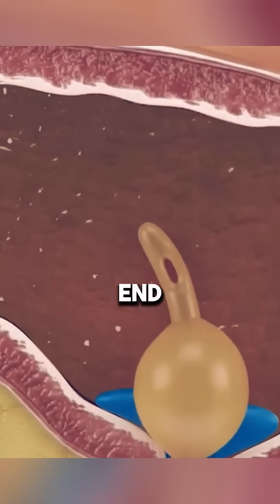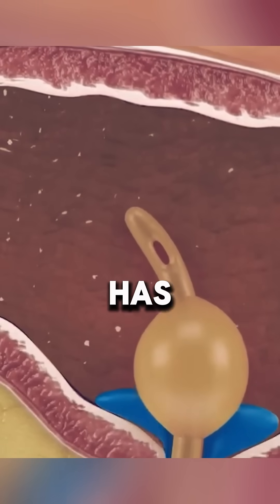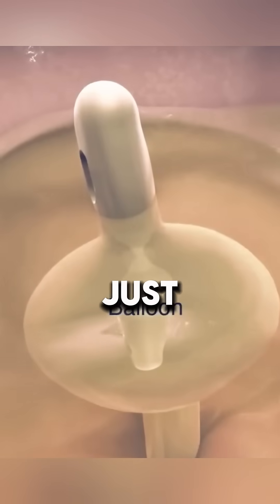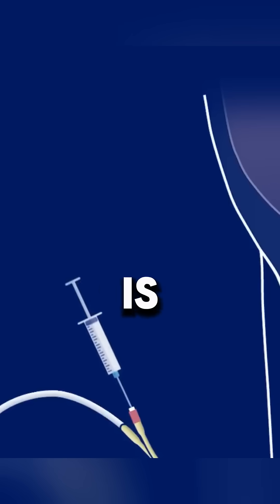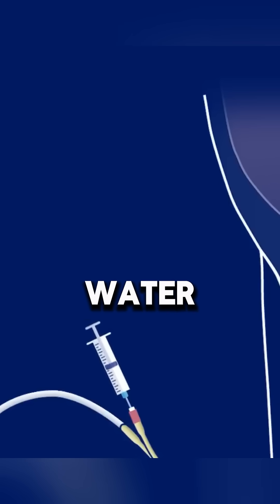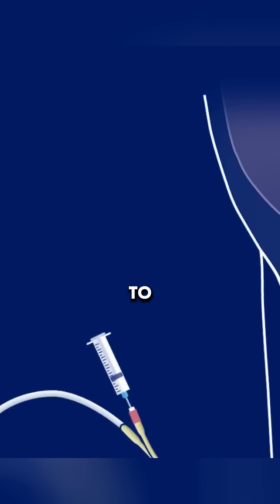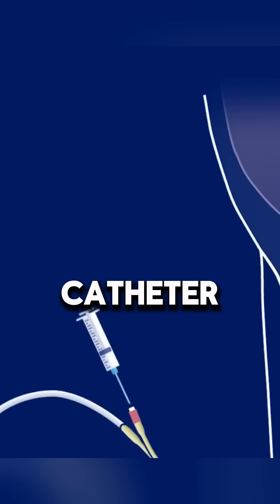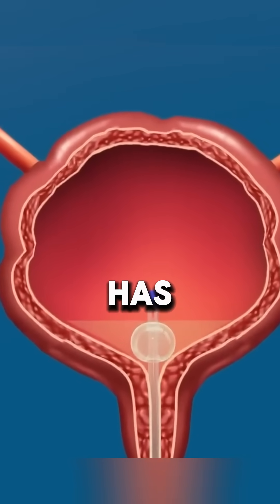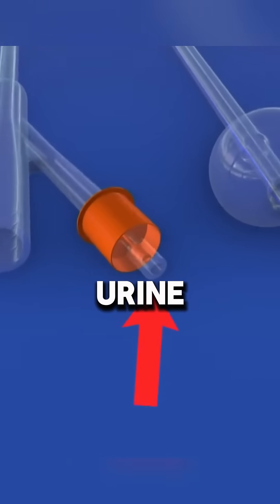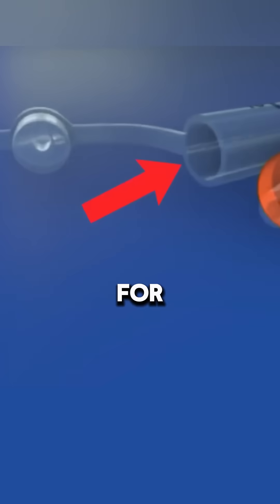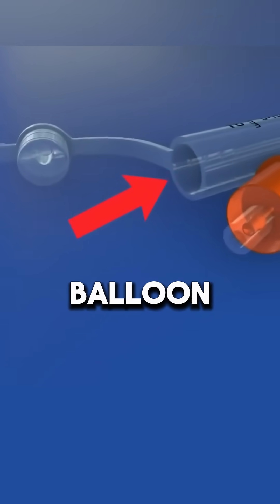One end of the catheter has a hole for urine drainage. Just below it is a balloon that is inflated with water once inserted to keep the catheter in place. The other end has two ports: one for attaching a urine bag that collects drained urine, and another for inflating the balloon with water.